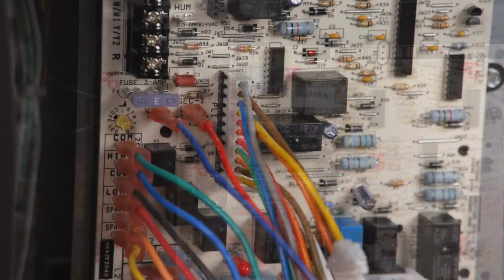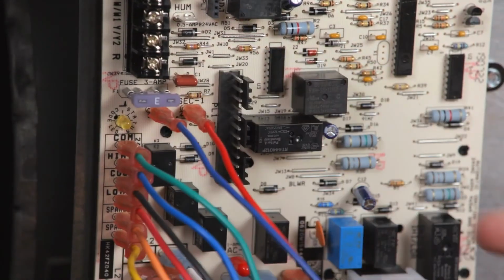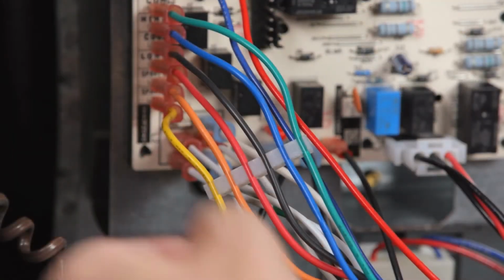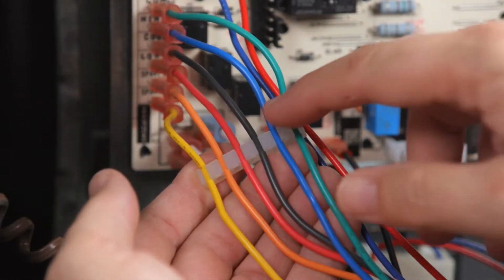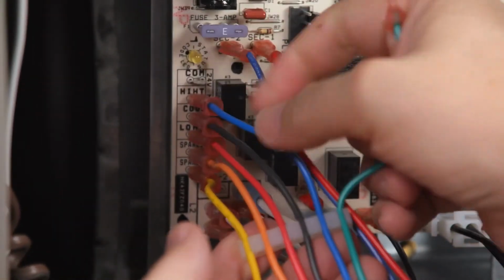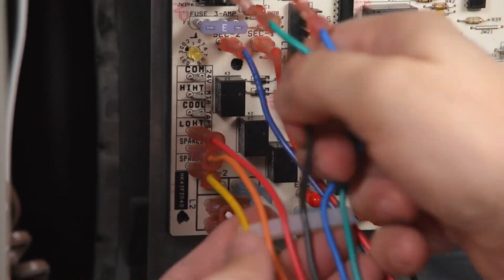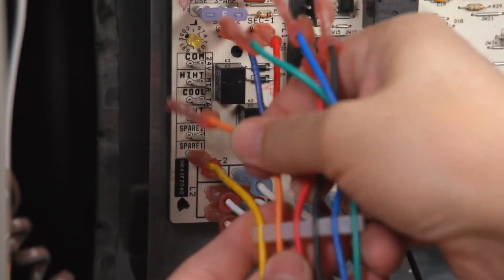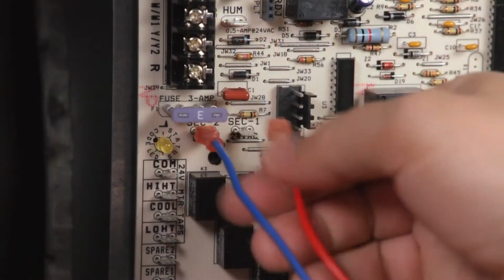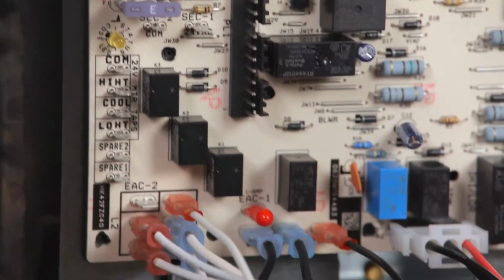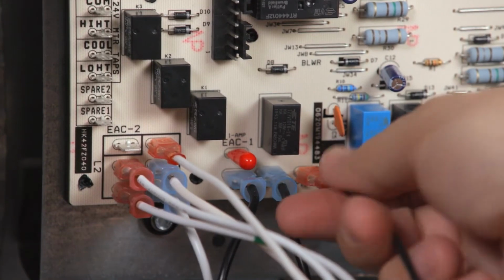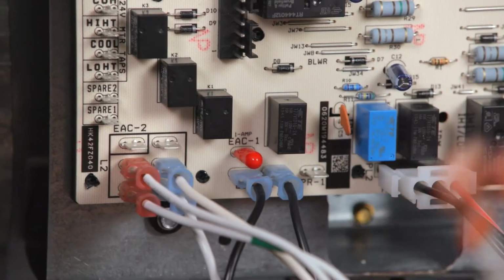Disconnect the thermostat wiring. Remove the Carrier inline plug. Take note of what color wires are going to each terminal. Remove the low-voltage blower motor wires for common, high heat, cool, low heat, and spares. Disconnect the 24-volt transformer wires and the 120-volt power and neutral transformer wires.